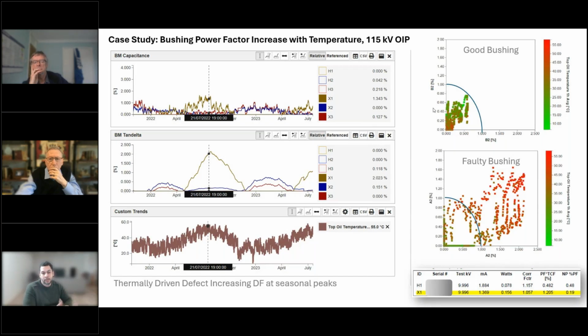But if you have a correlation between temperature and high elevated dissipation factor in bushings particularly, that's indicative of a specific type of defect. And this defect can eventually fail bushings. We've seen also the progression and the deterioration over years where the losses become higher and higher, and eventually the bushing faults.